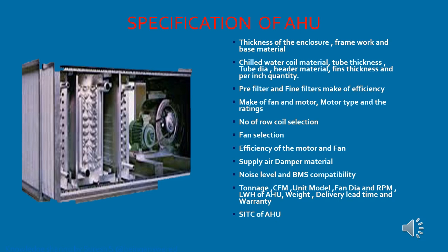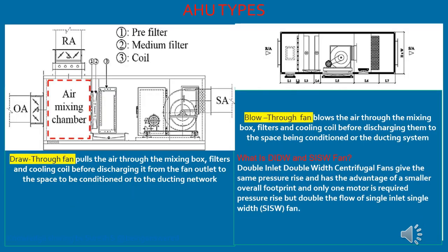Further specifications to check include: supply air damper material, noise level, BMS compatibility, tonnage, CFM, unit model, fan diameter, RPM, and the length, width, and height of the AHU, weight, delivery time, and warranty — for supply, testing, and commissioning of the AHU. These are the basic parameters which need to be confirmed in the AHU specification while placing an order.